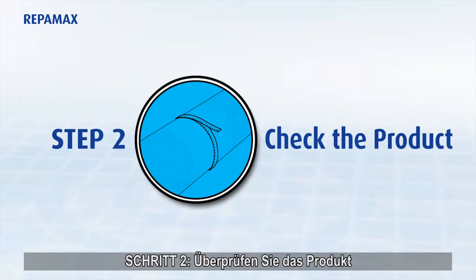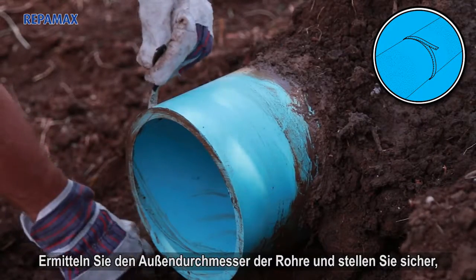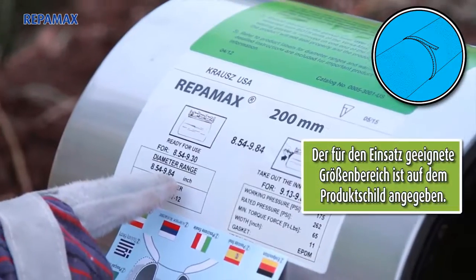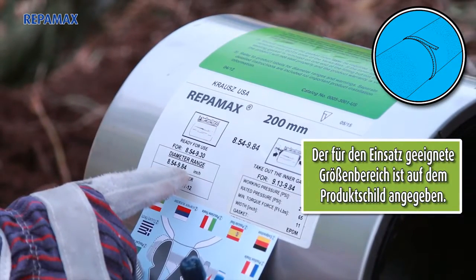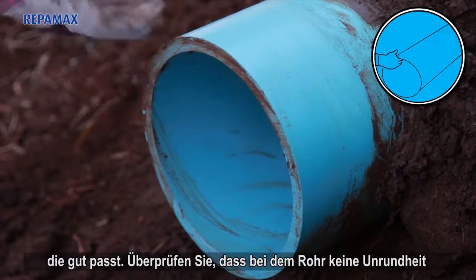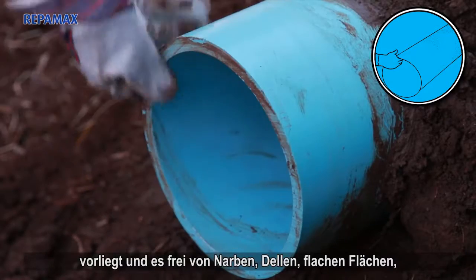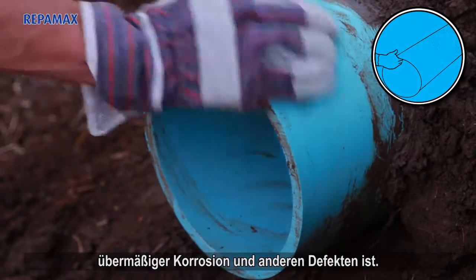Step 2: Check the product. Check the diameter of the pipes and verify the size of the Repamax for proper fit. Confirm that the pipe is not out of round and that it's free of scars, dents, flats, excessive corrosion, or other defects.